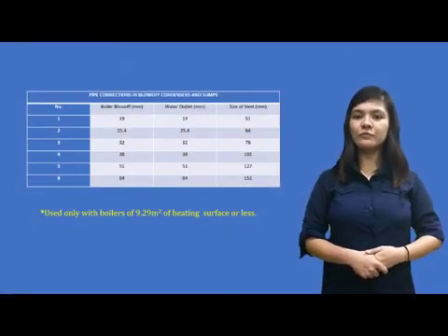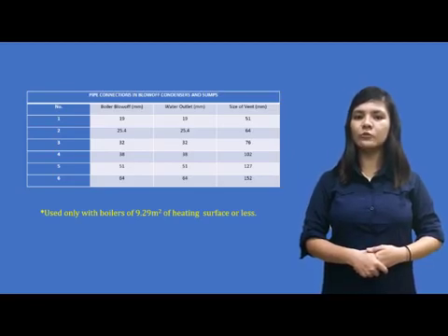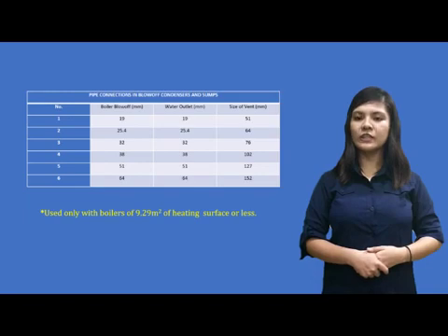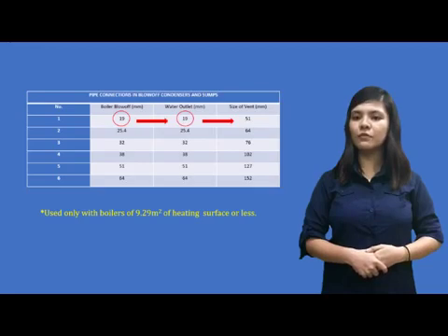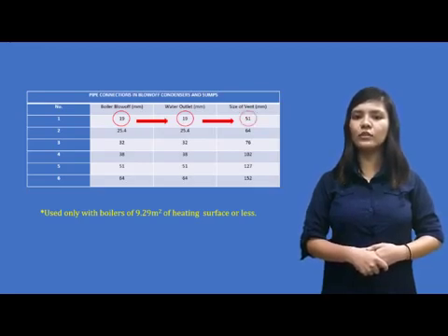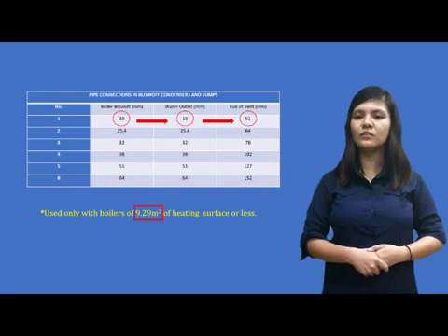Here's a table for reference showing the sizes of boiler blow-off, water outlet, and vent, which vary accordingly. For example, number 1: blow-off has a measure of 19 mm, which will also need 19 mm of water outlet and 51 mm of vent. Remember to use it only with a boiler of 9.29 m² of heating surface.